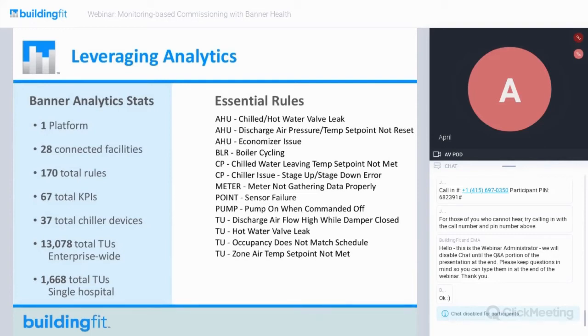The next one is for point sensor failures. This is really critical. There are just thousands of points out there collecting information in the real world and transmitting them into data. And if any of those go wrong, you've got garbage in and you're going to get garbage out. You're going to have bad results. So making sure that none of those have failed is critical as well. For pumps, I threw in here a kind of salute to overrides, which is a classic cause of drift when things get overridden and no longer work automatically and efficiently.